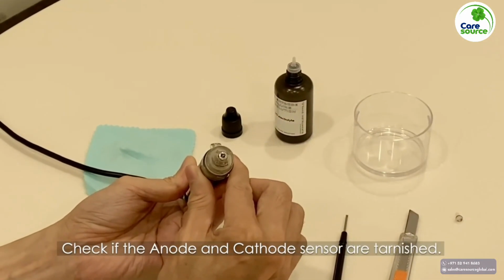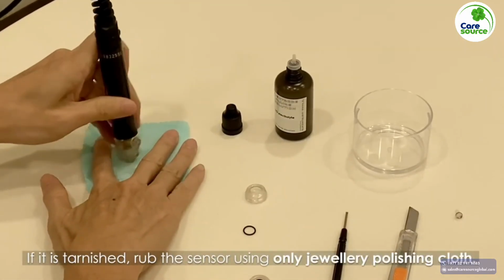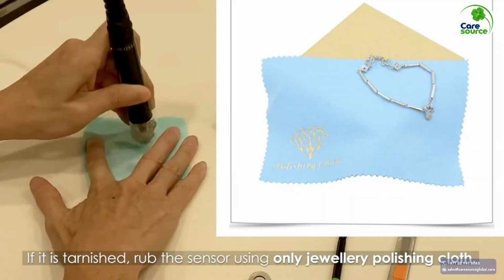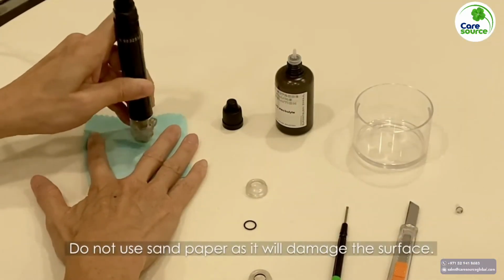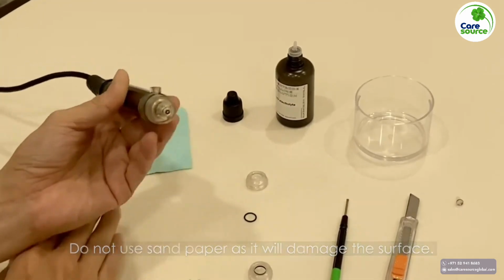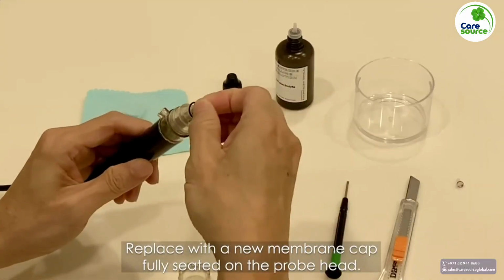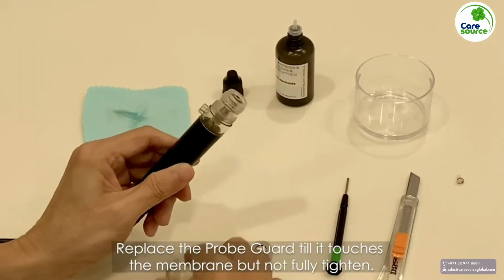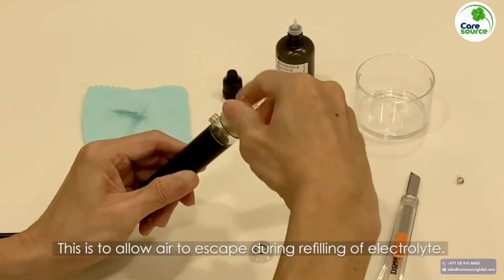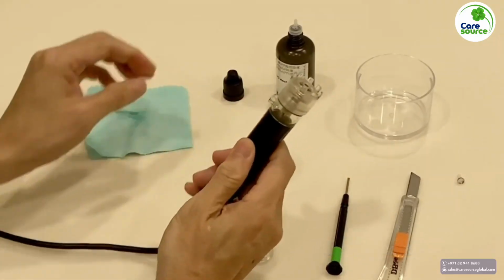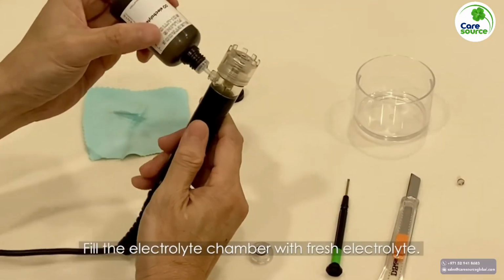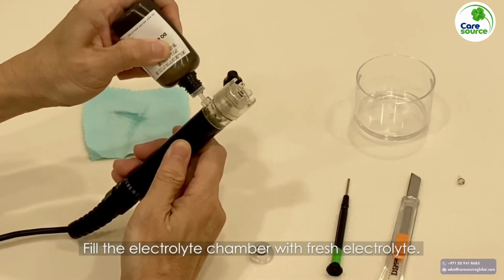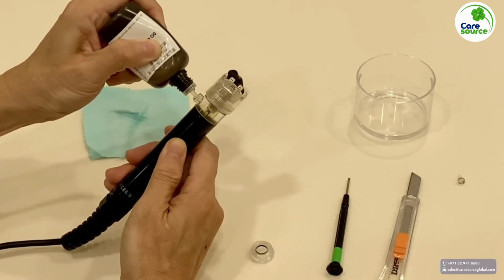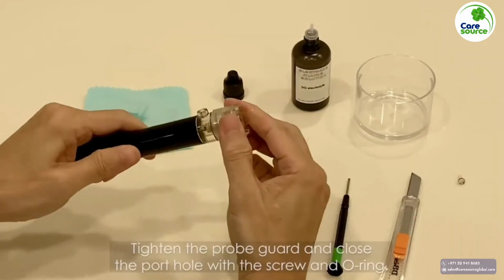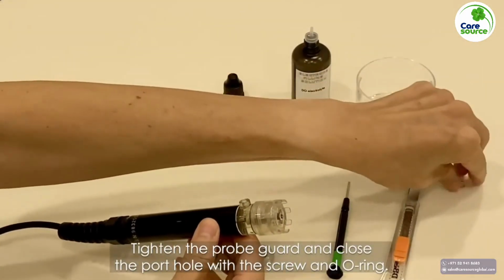Check if the anode and cathode sensor are tarnished. If it is tarnished, rub the sensor using only a jewelry polishing cloth. Be careful not to use sandpaper as it will damage the surface. Replace with a new membrane cap, fully seated on the probe head. Replace the probe guard till it touches the membrane but is not fully tightened. This is to allow air to escape during the refilling of electrolyte. Fill the electrolyte chamber with fresh electrolyte. Tighten the probe guard and close the porthole with the screw and O-ring.